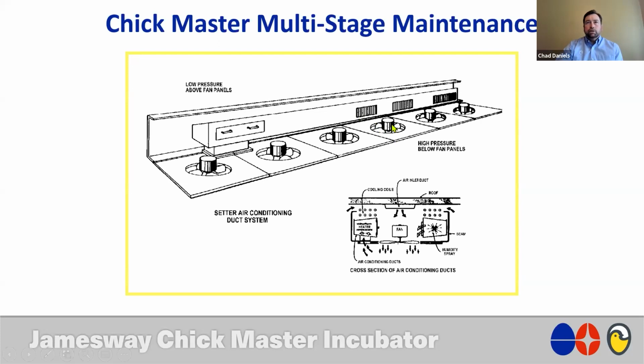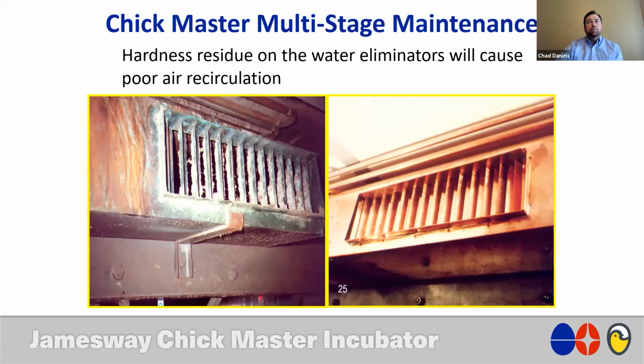But with good fan condition, good static and good negative suction draw here, these three fans work together to pull air through this duct that is fed from the other end of the machine. The duct on the other side works in reverse. So the condition of the fans and the condition of your duct is very critical in allowing a machine to heat properly, humidify properly, and exchange air from the front to the rear of the machine, so you avoid creating big temperature differences from front to rear. As an example, on the right you see a newer water eliminator, and with it being clean and in good condition, it's not going to cause any airflow restrictions, as opposed to the one here on the left in this illustration.